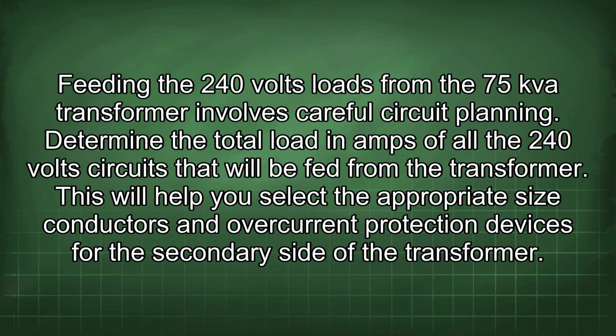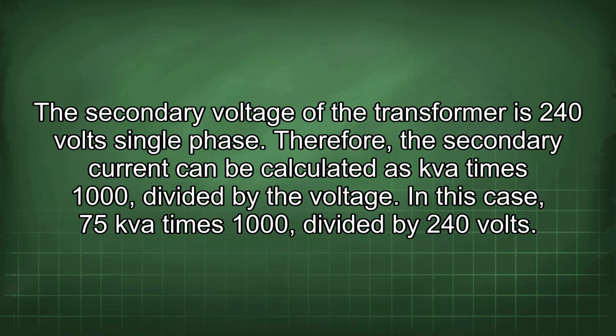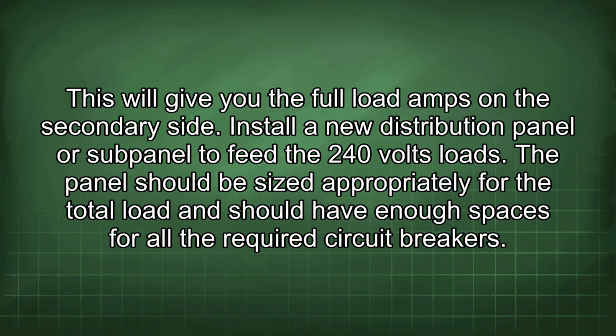Feeding the 240 volts loads from the 75 kVA transformer involves careful circuit planning. Determine the total load in amps of all the 240 volts circuits that will be fed from the transformer. This will help you select the appropriate size conductors and overcurrent protection devices for the secondary side of the transformer. The secondary voltage of the transformer is 240 volts single phase. Therefore, the secondary current can be calculated as kVA times 1000 divided by the voltage. In this case, 75 kVA times 1000 divided by 240 volts. This will give you the full load amps on the secondary side.